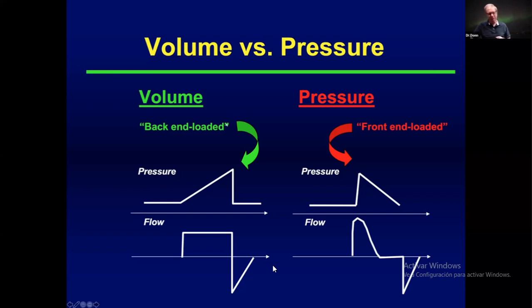Let's shift a little bit now, go to the left side here and talk about volume breaths. And here, I'm not talking about volume guarantee, I'm talking about true volume controlled ventilation, where the flow pattern is the so-called square wave. And what happens when the breath begins is there is a slight acceleration to a peak inspiratory flow level that is then held constant for the entire duration of inspiration until the exhalation valve opens and the breath is discharged. And what this does then is it results in a more slowly ramping pressure and volume delivery, such that peak pressure and peak volume delivery occurs at the end of the breath, at the end of inspiration. And the net effect here then is we have really a slower, kinder, gentler delivery of airway flow, such that you're more likely to have more uniform inflation of the lung than you would if you were using this type of accelerating, decelerating flow waveform.